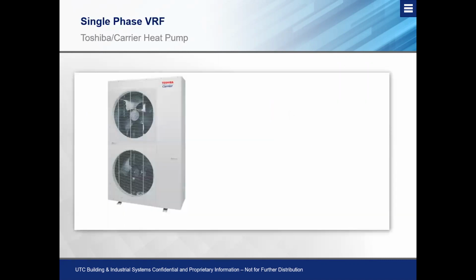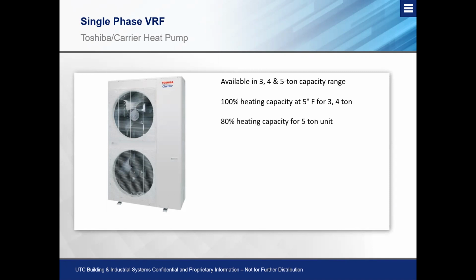So with the Toshiba Carrier single phase VRF heat pump, these are available in a 3, 4, and 5-ton capacity range. We're able to give you 100% heating capacity at 5 degrees for our 3 and 4-ton models. And on our 5-ton unit, we're going to give you 80% heating capacity at 5 degrees. We have the ability to connect up to 9 multiple style indoor units on a 5-ton system. On a 4-ton, we can connect 8, and on a 3-ton, we can connect 6. So again, it depends on the tonnage for the maximum connected number of indoor units.